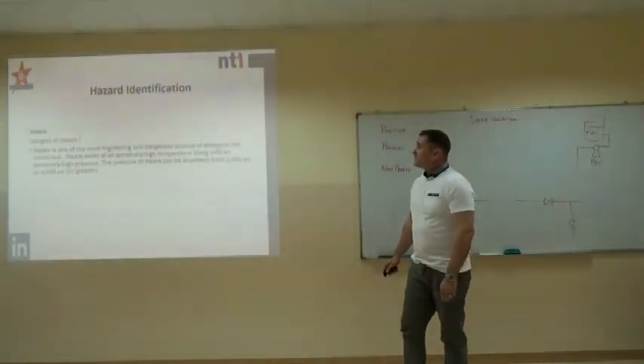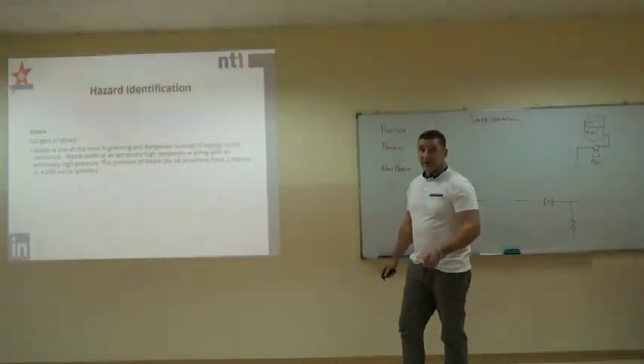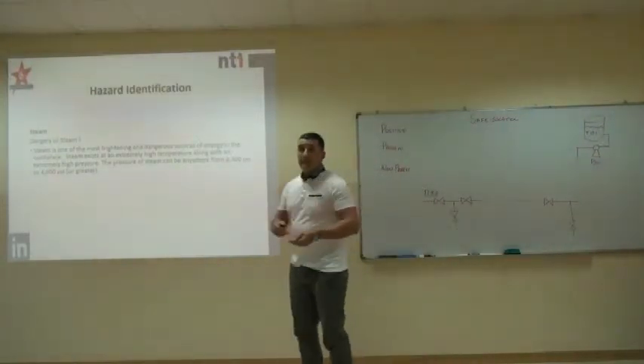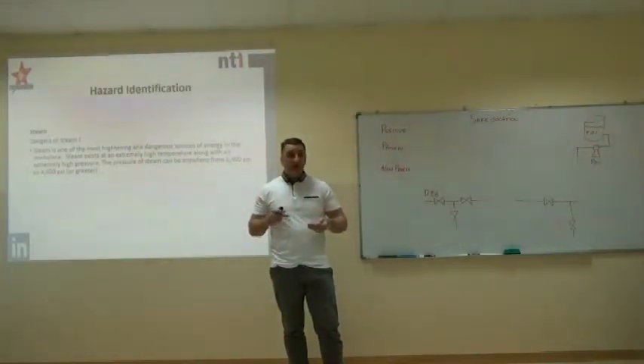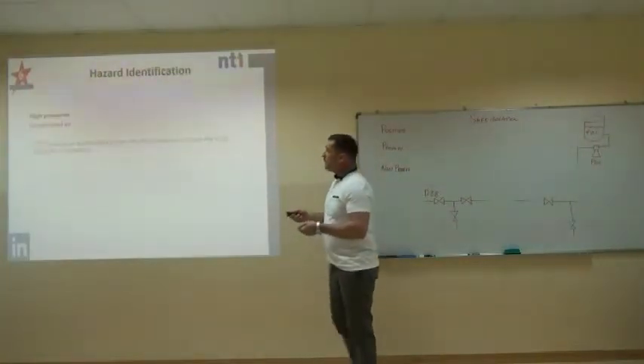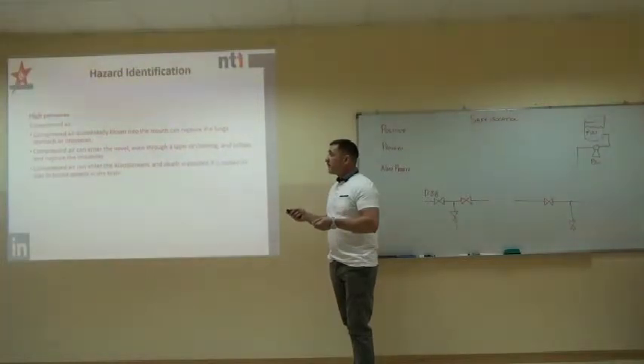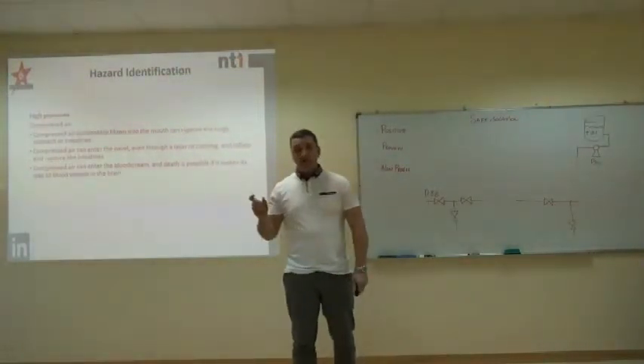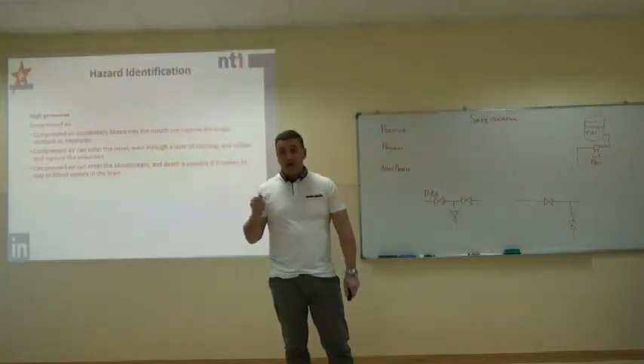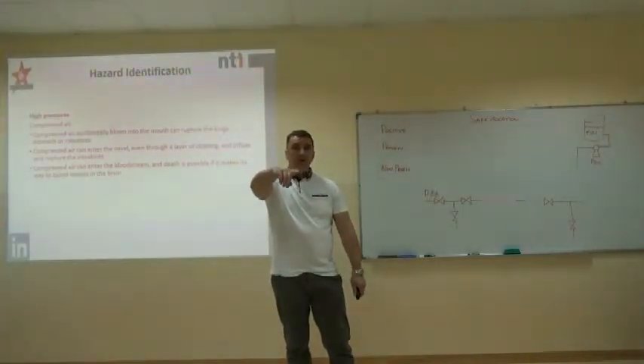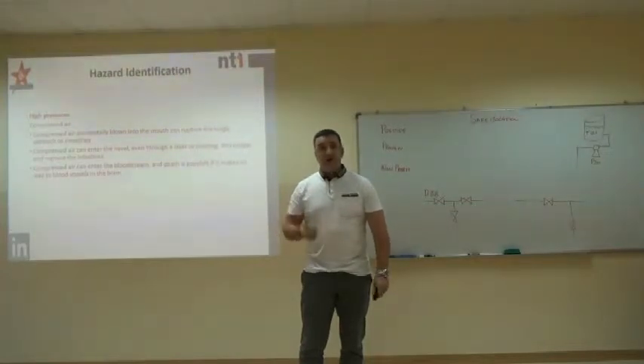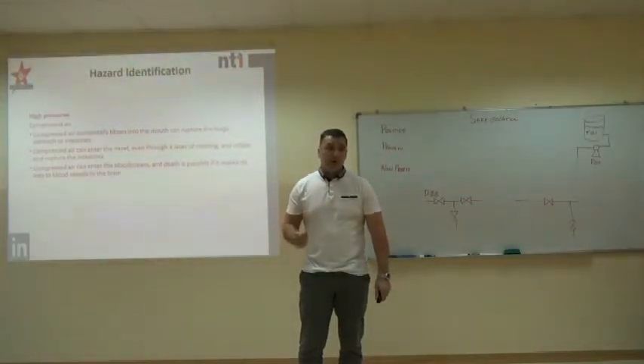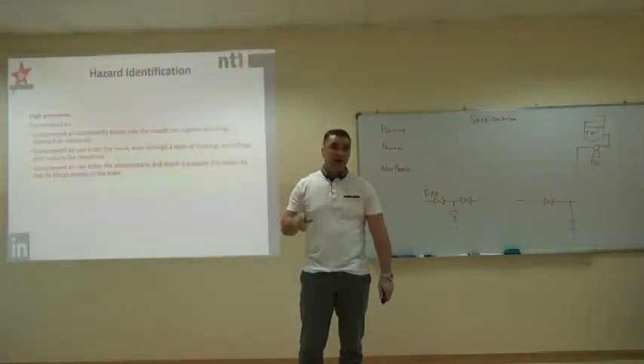Hazard identification. Steam: the effects are obvious — high temperature, high pressure. It can burn our skin, and if we cover a certain percentage of our body in burns we will nearly always die — there's no treatment for that. Compressed air, again, if we put that through any orifice, cut or wound in our body it can cause extreme damage, even at pressures as low as 4.5 bar as we use for controlling control valves. We used to blow ourselves off with air guns — it's very dangerous, we shouldn't do it. Always treat compressed air with respect and always isolate it.